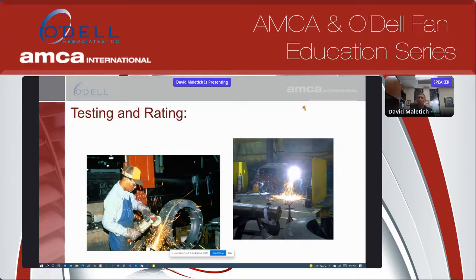They'll pick a size, we have to build it, submit it to AMCA, and they have to be able to replicate our catalog data, again, plus or minus 2.5% flow pressure, 5% energy consumption. If we can't do that, or they can't do it, we potentially lose our validation for that product line. So that's what ensures that over the life of a fan, that it still performs, even though we're still fixturing it and those things might go out of tolerance, that they're going to perform to this catalog. So it's a really good methodology to pair brand A to brand Z, and making sure that what you're getting is something that's going to perform equally and is directly comparable.